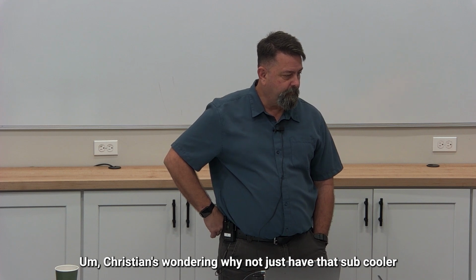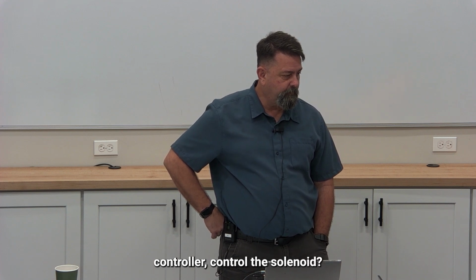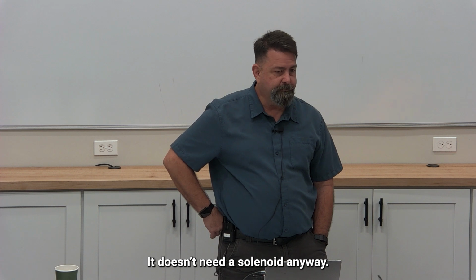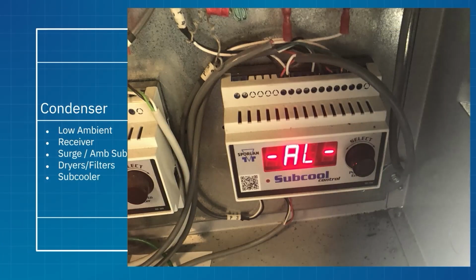Christian's wondering why not just have that subcooler controller control the solenoid? Well, because it doesn't have a digital out setting in it. It doesn't need a solenoid anyway, and it really doesn't, because the TXV is gonna close. It's gonna go to zero and it's gonna close. Right, it might leak a little bit, which is why they want a remote monitor. No, refrigeration, right, now we're talking about this Sporlan version of that.